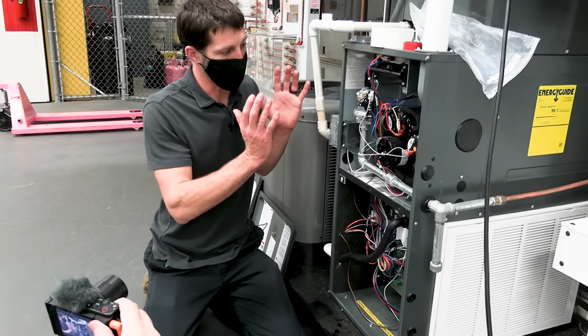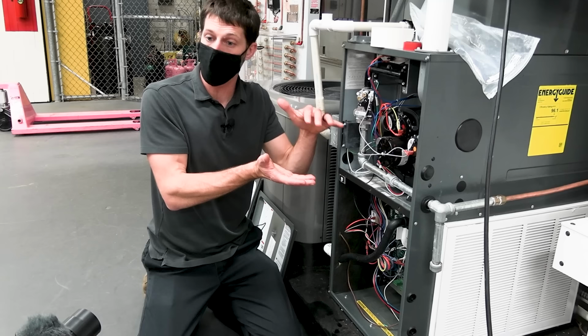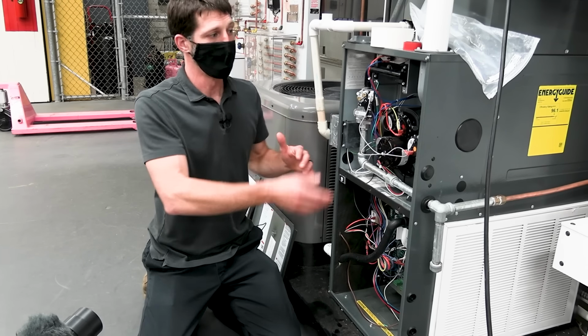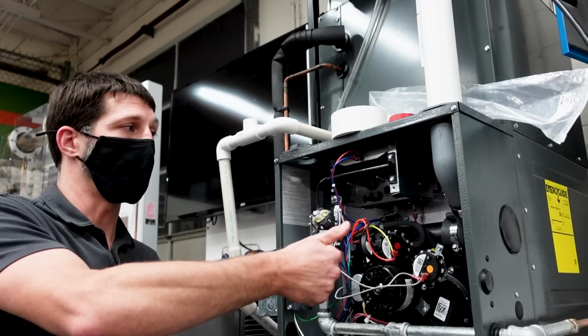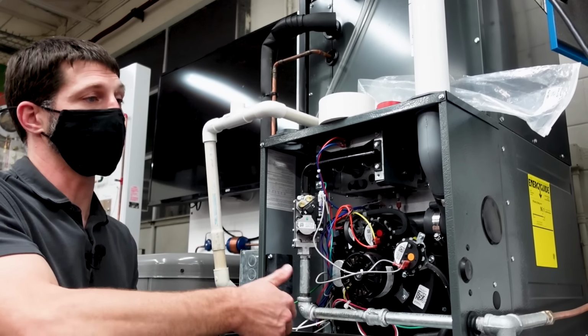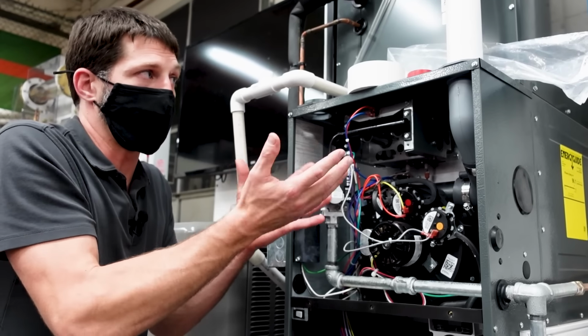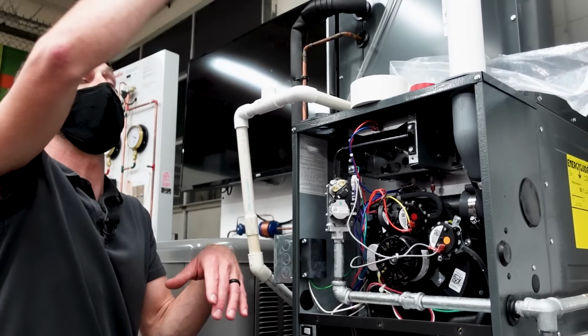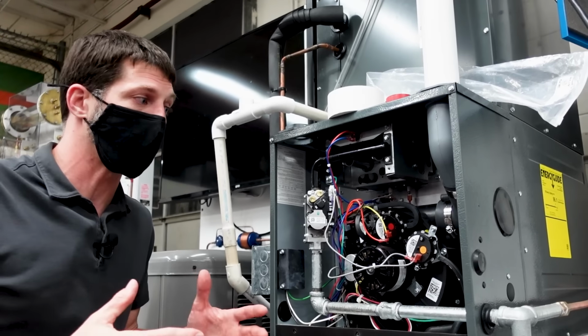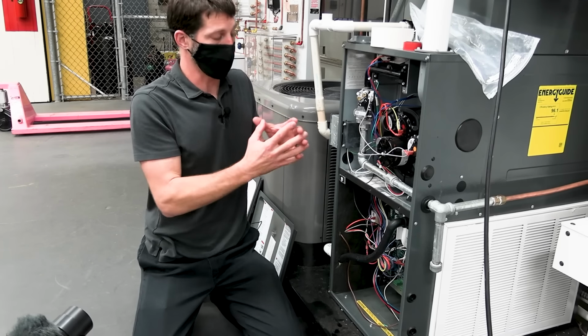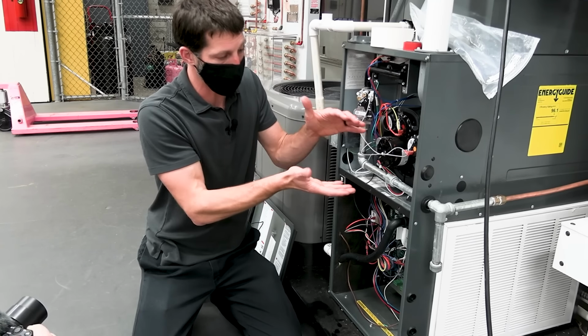So what I was saying is an 80% efficient furnace doesn't have a secondary heat exchanger, because what happens is the exhaust temperature is much higher. And so what's happening is the condensate is not able to form, the water vapor is not able to condense, and it just goes right out the exhaust pipe on an 80% efficient furnace. 90% efficient furnace, you have a larger heat exchanger because you have the primary and the secondary.